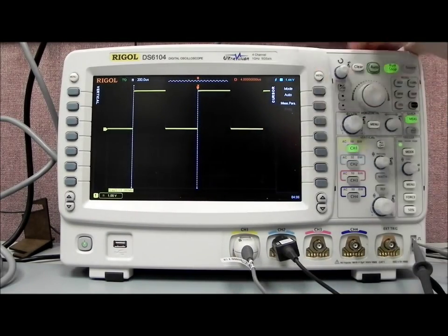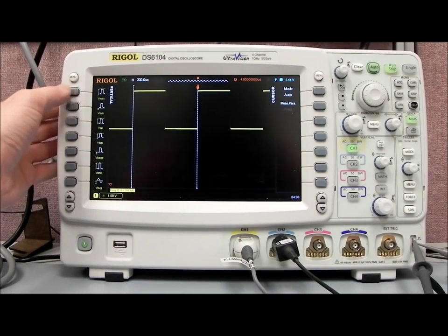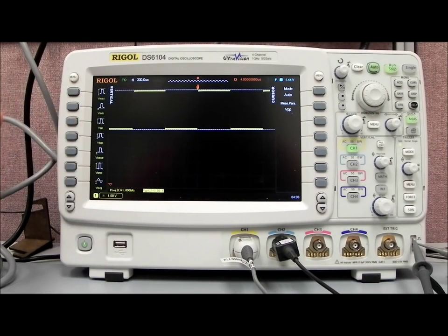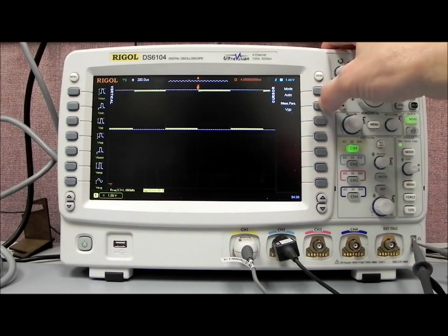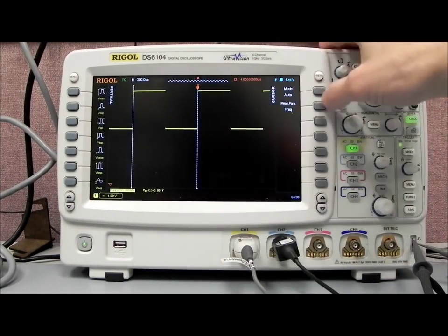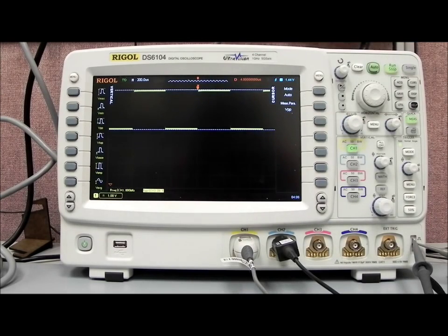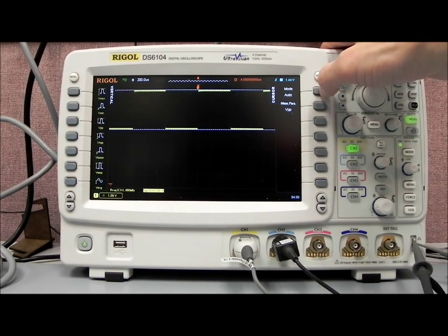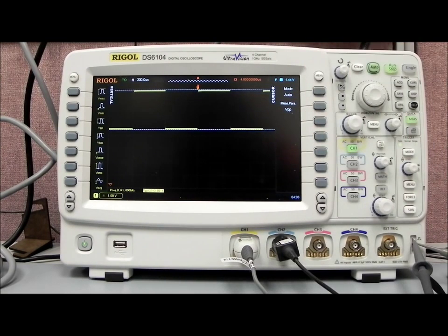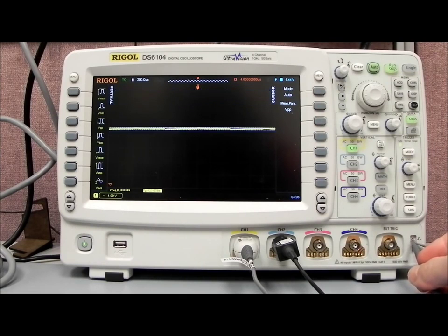We can actually select if we had a number of parameters. Let's go to vertical and we'll do VPP. And so now we can select between the different values that we have available, and the cursors will then indicate where we're making those measurements, which can be extremely helpful when you're doing some really quick measurements on a time-varying scale. If we were changing this particular waveform, let me do a little manipulation.